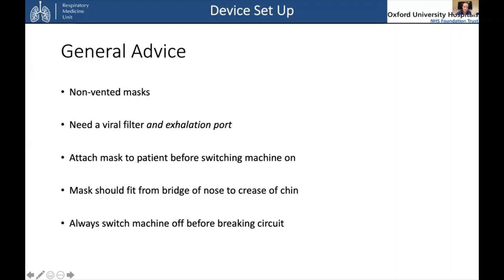General advice: attach the mask to the patient before switching the machine on, mainly because it's impossible to get the mask fit right once the machine is on, as it's blowing air at the patient. When you see the patient and want to set them up, the mask should fit from the bridge of the nose to the crease of the chin. It's quite common to see a mask sitting over the bottom of the chin, which means there's a lot of leak coming out, so do have a look at that and try to size it right.